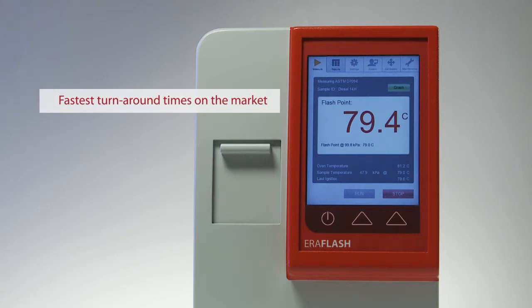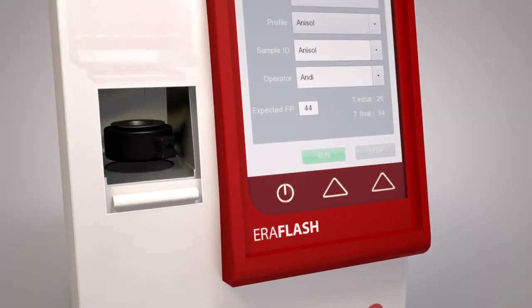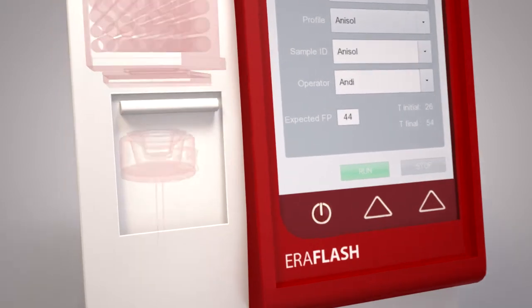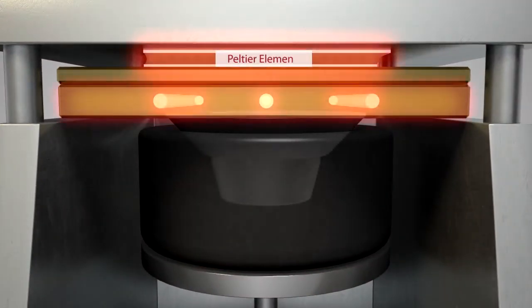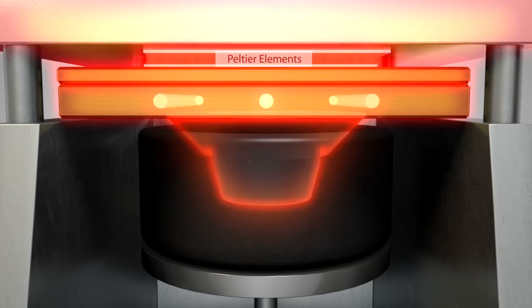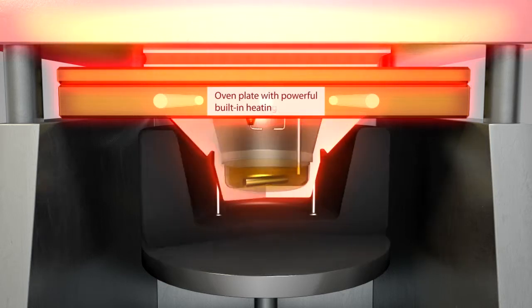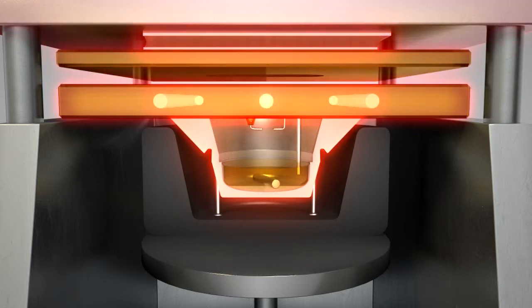The resulting turnaround times are significantly shorter than those of all other available flashpoint testers. A close look at the design principle reveals three reasons why Eralytics' Peltier Boost Technology is so effective. One: the Peltier elements are disconnected automatically once a certain temperature has been reached. Two: the built-in heating rods in the oven plate continue heating while the Peltier elements move up, which protects them from high temperatures.